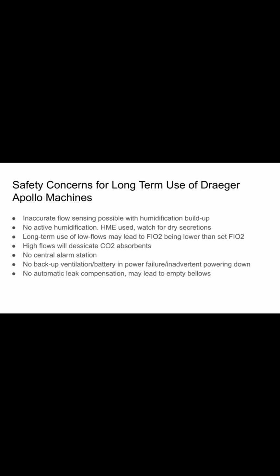We are going to be using relatively low flows, which over time in this circle system can lead to the FiO2 that we're actually delivering to the patient being lower than what we are setting on the ventilator. So make sure you're mindful of actually checking the gas analyzer for its FiO2 and making sure that it is reflective of what you have set with your oxygen levels that you want the patient to be receiving. Higher flows, which we will need to use to try and keep the circuit drier, may desiccate our CO2 absorbent, so be on the lookout for that.